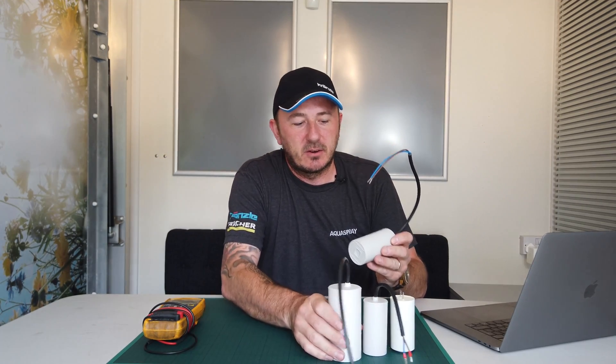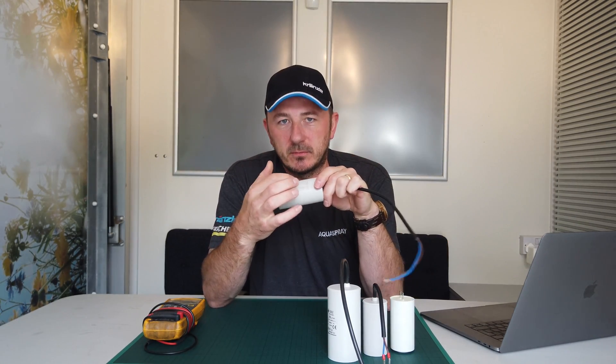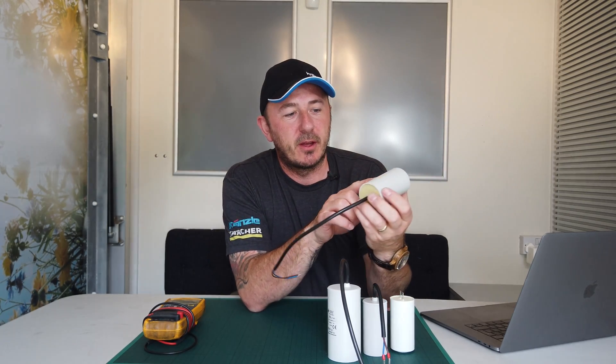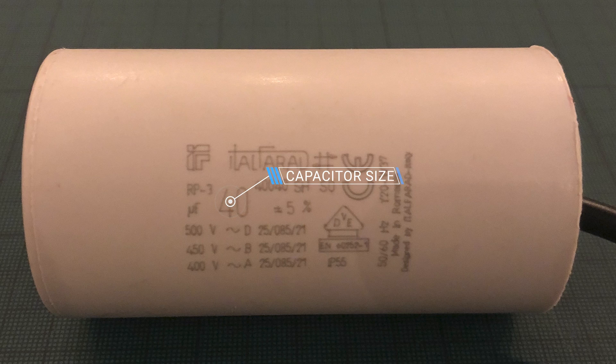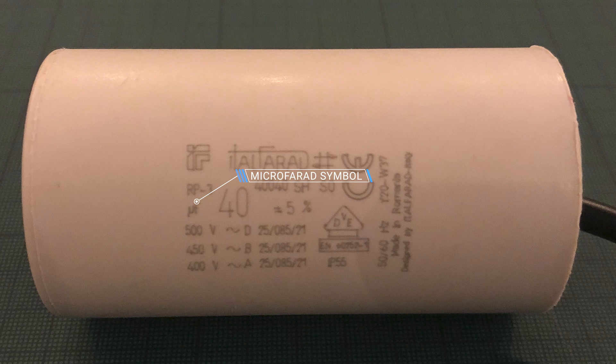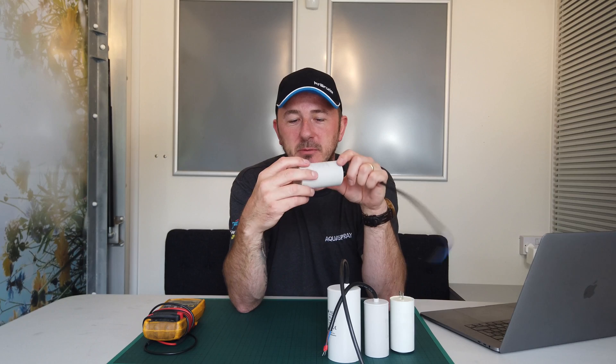The most common one we use in the Kränzle world for the portable machines is the 40 microfarad. The numbers on the actual specification sheet — you're looking for the biggest number on there, which will indicate the microfarad. The symbol, which I'll put up here, looks like 'UF', and it'll usually say there's a tolerance of five percent plus and minus.